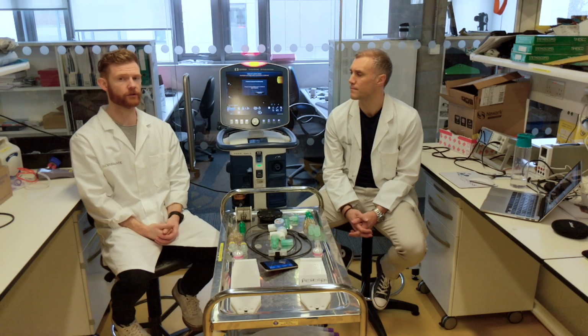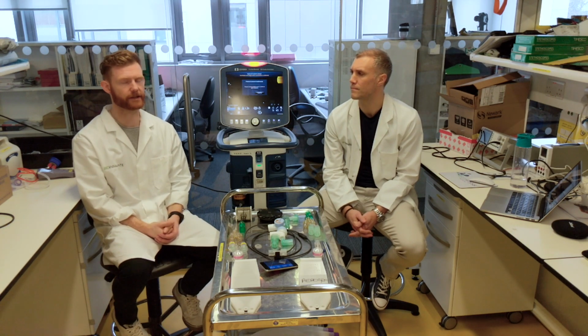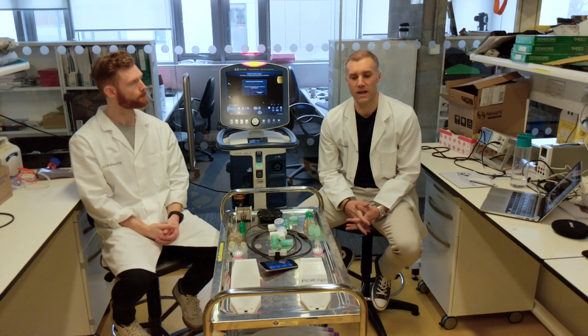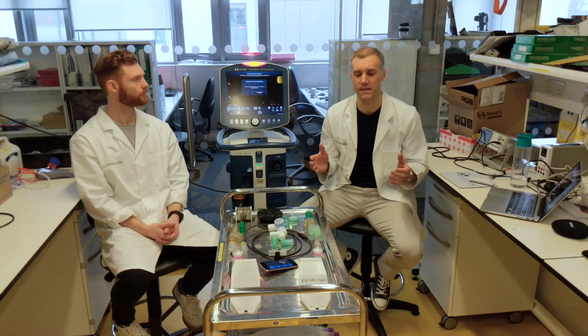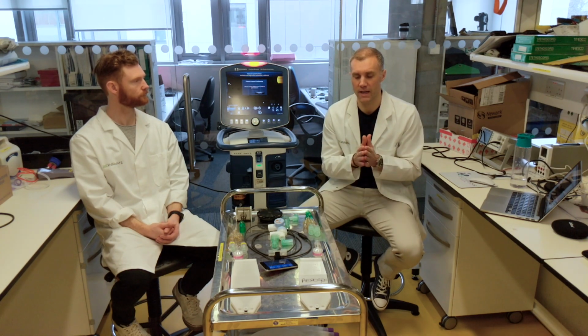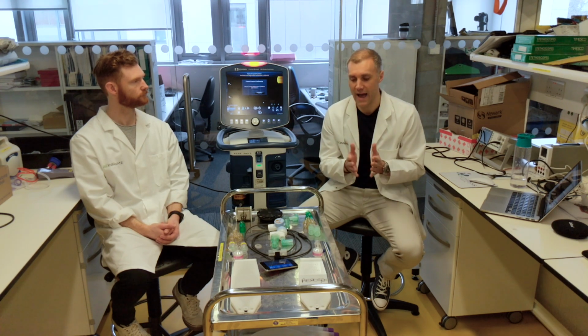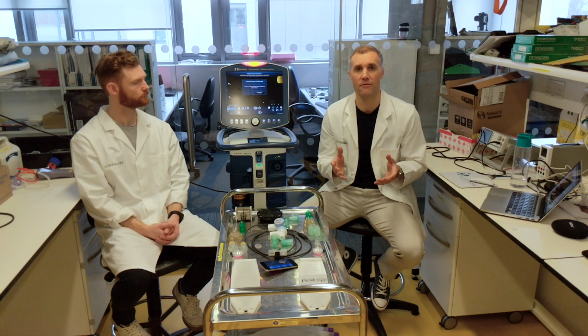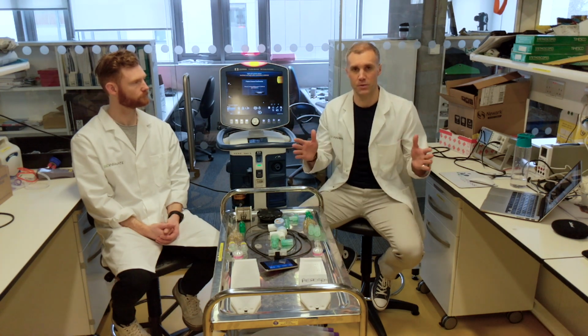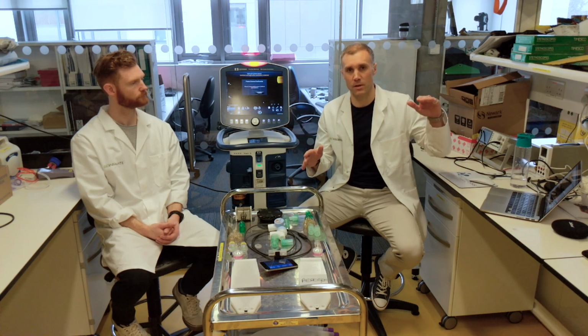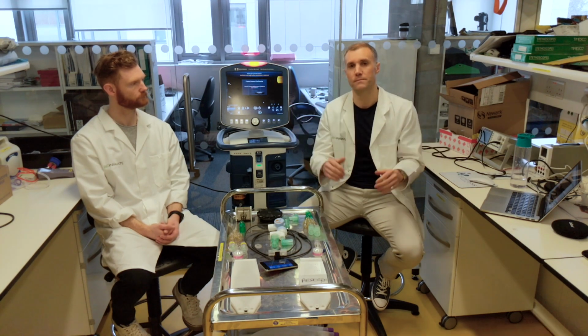We have been focused on a stream looking to address the shortage of invasive ICU ventilators. And over the last couple of weeks, we've conducted hundreds of tests and we've iterated many times. Close and constant clinical feedback, strong industry support, and a highly motivated team have allowed us to think fast, to work fast, and to work smart. We believe we now have a safe system that allows one ventilator to be shared between two patients with a titratable tidal volume and pressure.